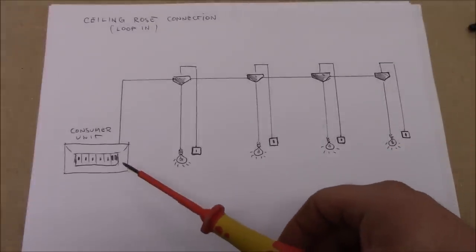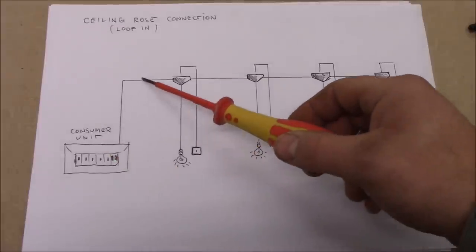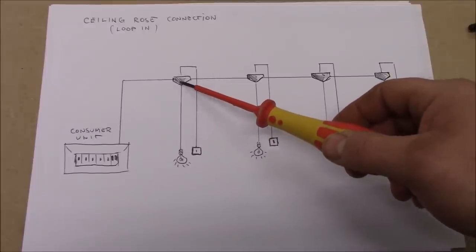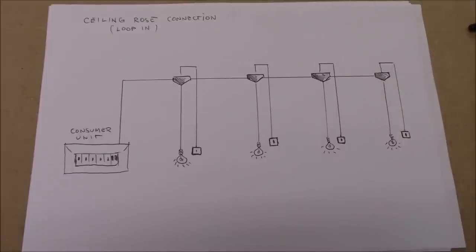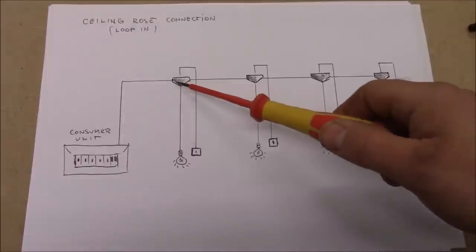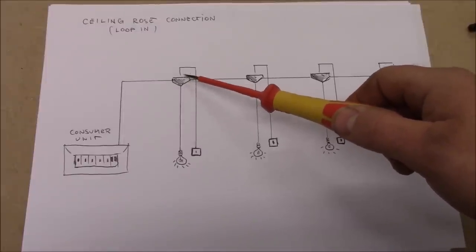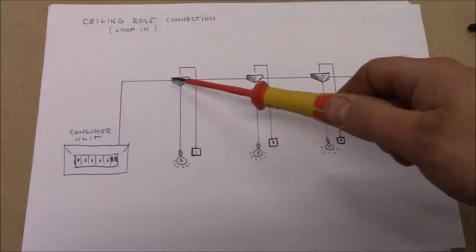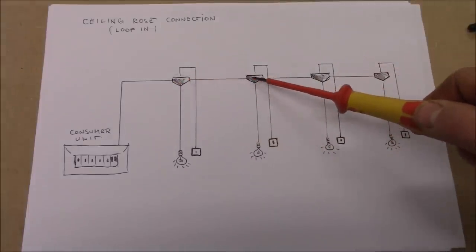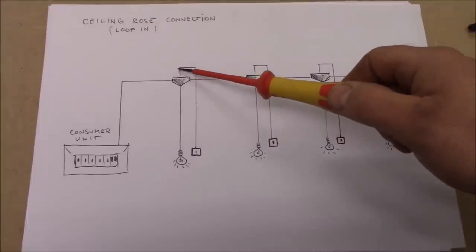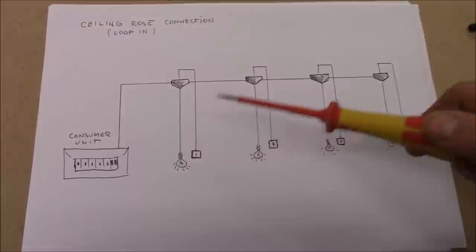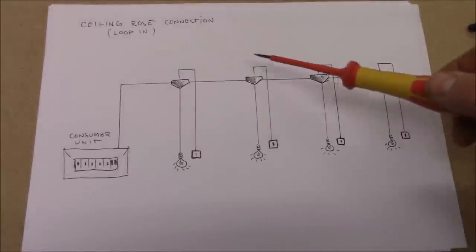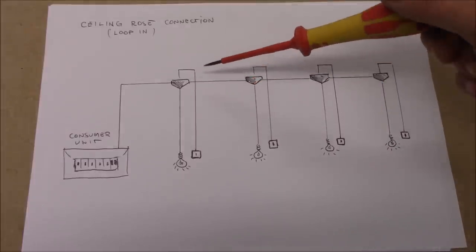Basically, the cable from the consumer unit goes to the first ceiling rose, then from that one to another, then to another, and so on to the end of the circuit. All circuits are radial — starting at the consumer unit and finishing at the last point. In every ceiling rose there are three cables: one coming from the consumer unit or previous light, one going to the next room, and one going to the switch, plus the flex cable going to the light fitting.